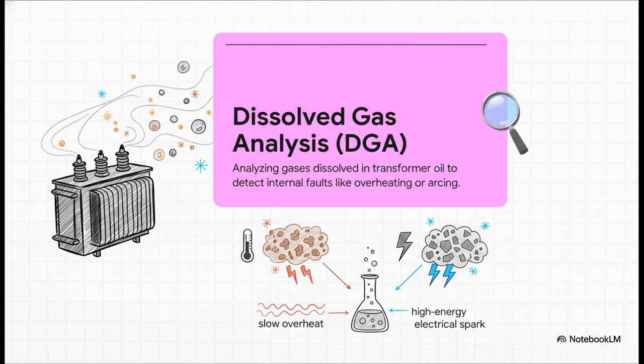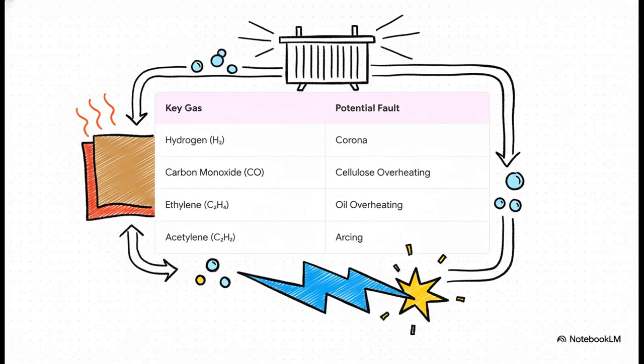The idea is that different kinds of stress, like a slow overheat versus a high-energy electrical spark, break down the oil and insulation in different ways. And each type of breakdown creates unique key gases that then dissolve into that oil. So, by analyzing a sample of that oil, engineers can read these signals like a detective. As this table shows, finding a lot of carbon monoxide points to the paper insulation getting too hot. But finding acetylene? Whoa. That's a major red flag for arcing, a really serious electrical fault that could lead to a big failure. Each gas tells a different part of the story.